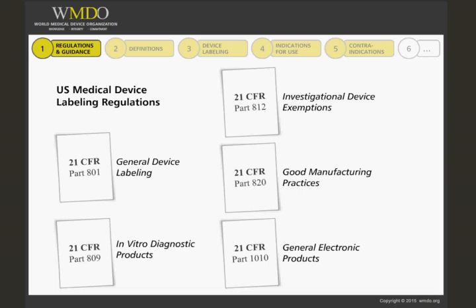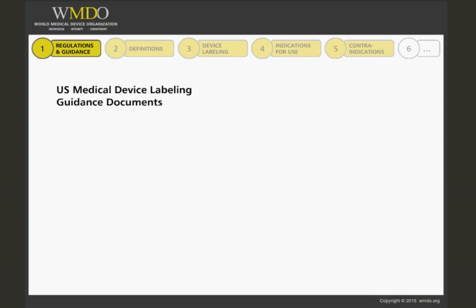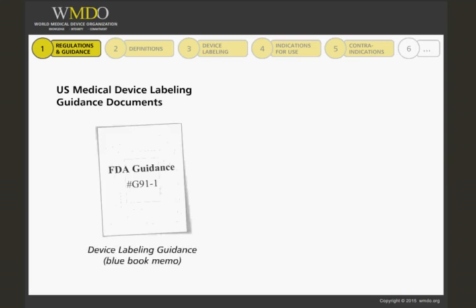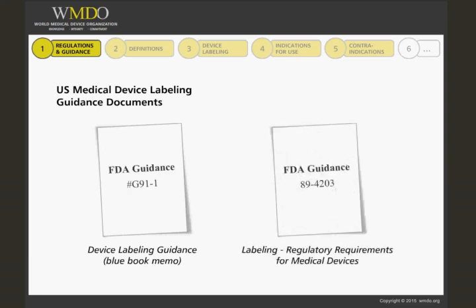It is always recommended to use the original text sourced from the relevant webpages when preparing regulatory documents. In addition, two labeling guidance documents are necessary to understand and perform the right steps. We have first the Device Labeling Guidance Blue Book Memo. Then there is the document entitled Labeling, Regulatory Requirements for Medical Devices. We will cover and cite much of the content in these two guidance documents during this course, and the web links for them are comprised in the references list that is part of your course resources. Go there, read them, and use them.